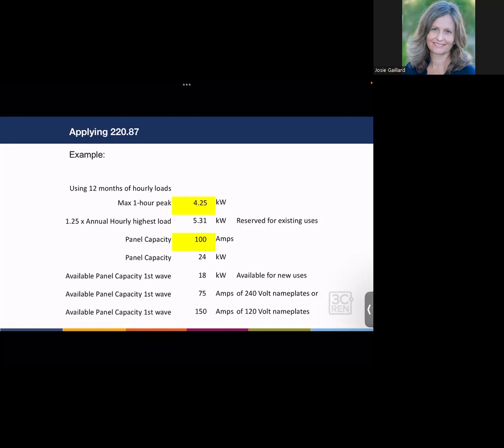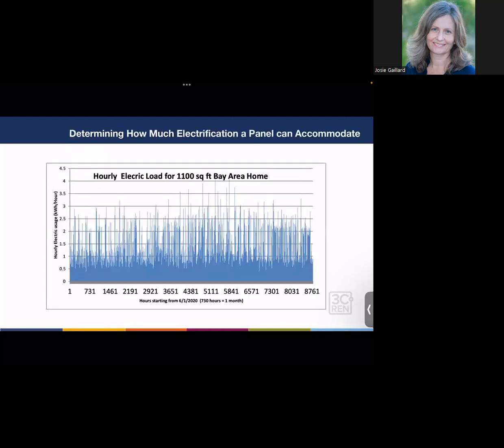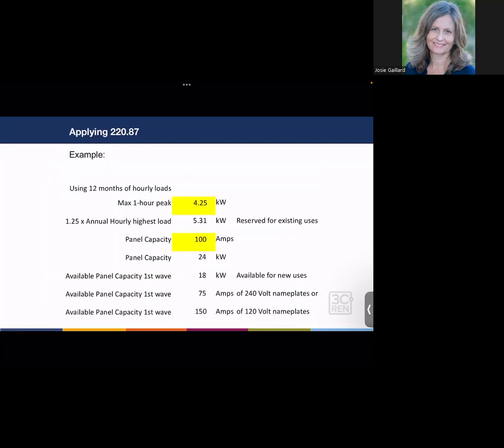Okay, so let's go back and do another example of 220.87. This is probably referencing this graph where the peak load was a little over 4. So let's assume the max 1 hour peak was 4.25 kilowatts. We multiply that by 1.25, that factor that the code prescribes, to get 5.31 kilowatts. We know the panel capacity is 100 amps. In other words, 24 kilowatts. So 100 amps times 240 volts equals 24 kilowatts.